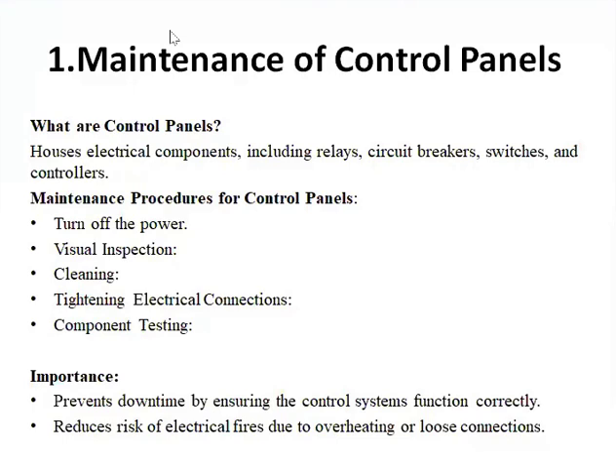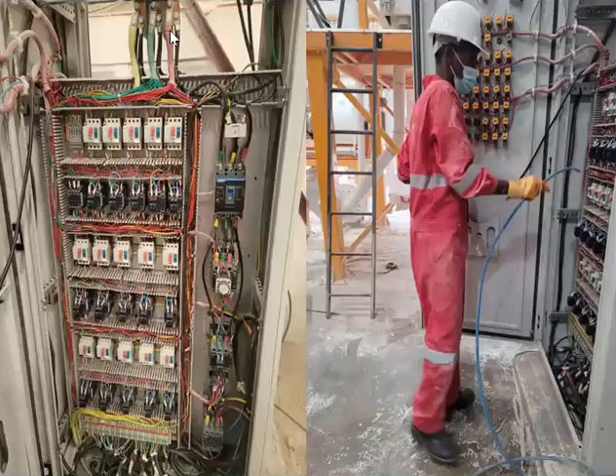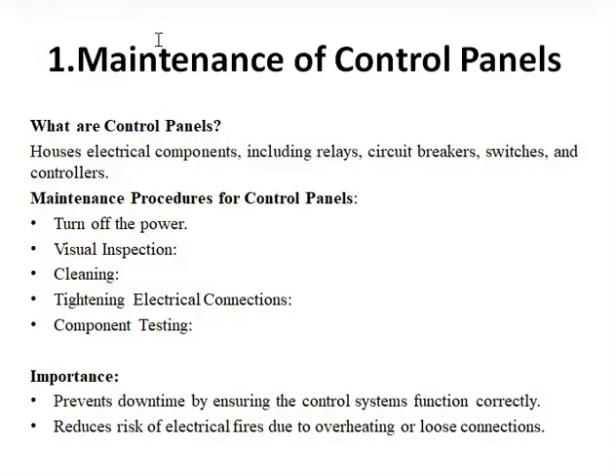So these are the maintenance procedures that one can follow whenever doing maintenance on a control panel. First of all, you have to turn off power. We always have a main circuit breaker here on top. Whatever you do, before starting maintenance, always ensure that power is turned off. I also do some visual inspection. I inspect the sparks. If they are beyond what I expect, or if it is an abnormal spark, then I act immediately. That could be as a result of a loose connection or overload to the motor.